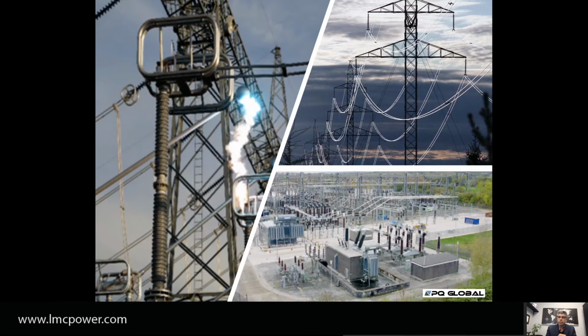There's arc flashes, or there's just simple maintenance. When you have a substation that transfers from one substation to the other to do maintenance, or they have power factor correction capacitors, or anything that has a large amount of current being transferred from one end to the other in a quick manner, then it's going to generate current going through the electrical utility lines into your facility.